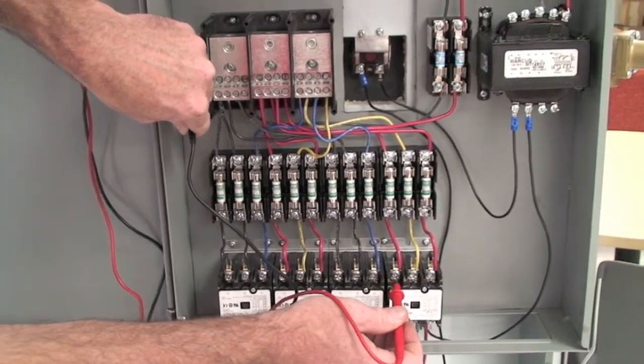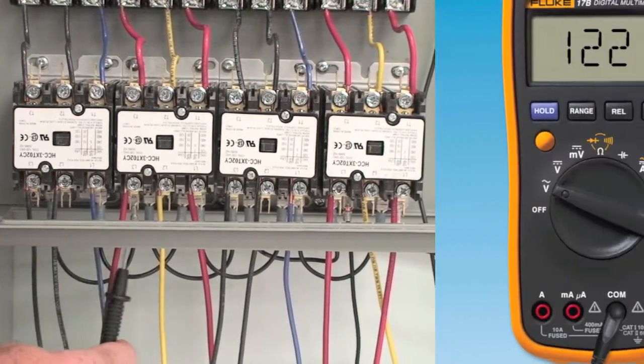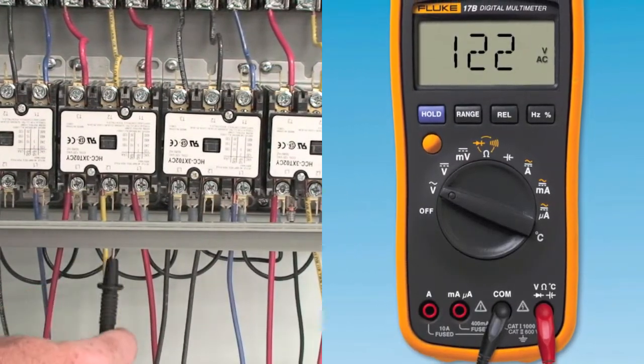If no voltage is measured, replace the corresponding fuse. Next, move the leads from T1, T2, and T3 terminals to the bottom terminals labeled L1, L2, and L3 of each contactor.